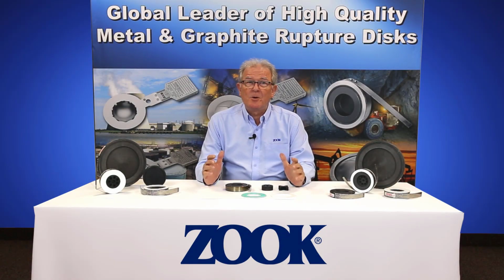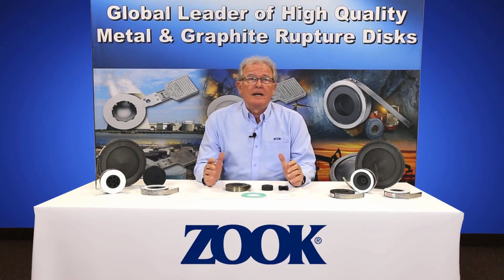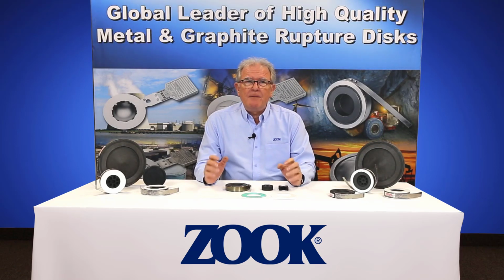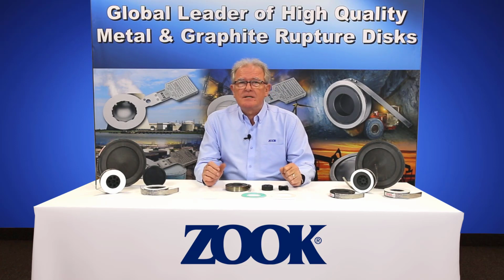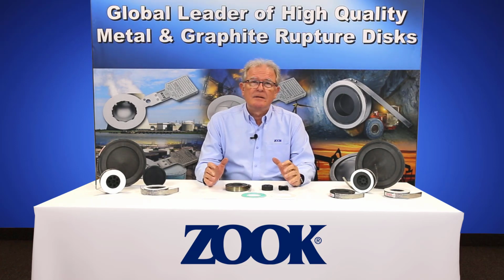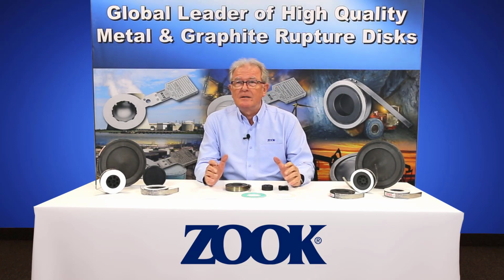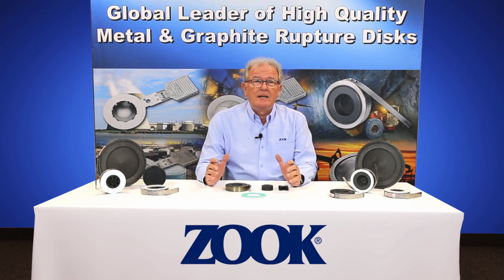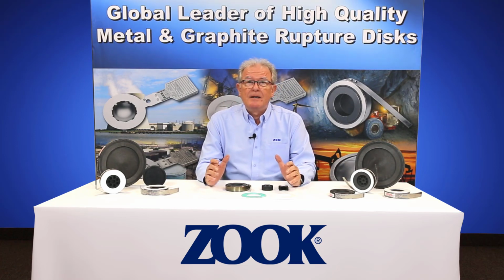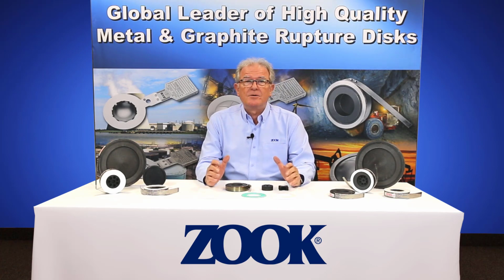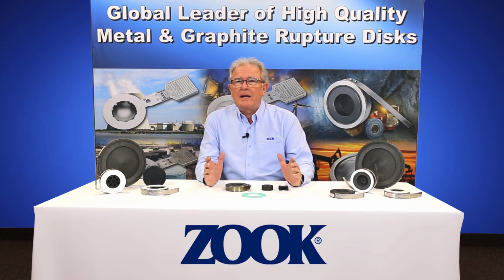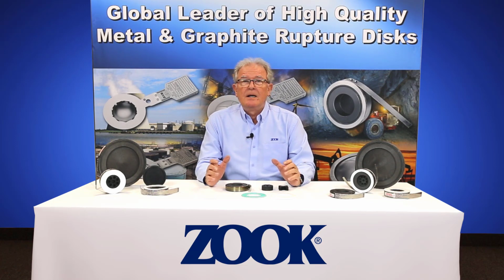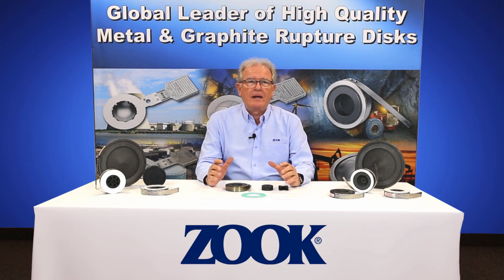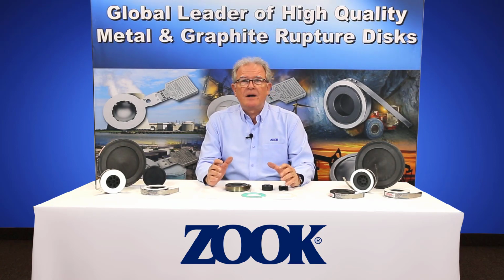So to answer the original question, why use graphite as a material for rupture discs, impregnated graphite has a low tensile strength, it is inert, does not give ion contamination, is highly corrosion resistant, and has good temperature stability, making graphite a first-class solution. Eventually, metal rupture disc technology improved and lower rated pressures were made available. But today, graphite rupture discs play a very important part in providing an overpressure relief device solution.